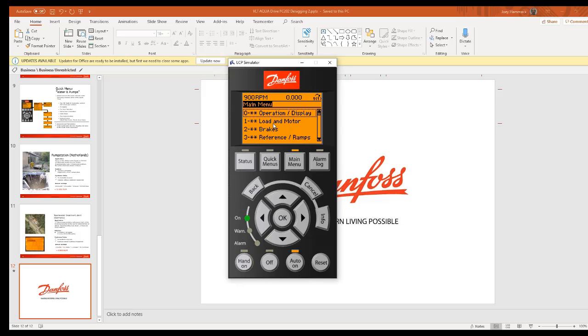Yes. There's a question about the recommendations. How do they know if customers should choose between the preventative DERAG versus the reactive DERAG? It's mostly application specific. As I showed at those two places where this was done, it was based on what's going on. Where the one was getting clogged with towels a lot, it was best to have the reactive mode, because it could happen at any time. So while it's pumping, a large towel or rag comes in, hits the impeller, the power goes up, it's clogged, then it can run through the cycle, clear itself, and continue to run.